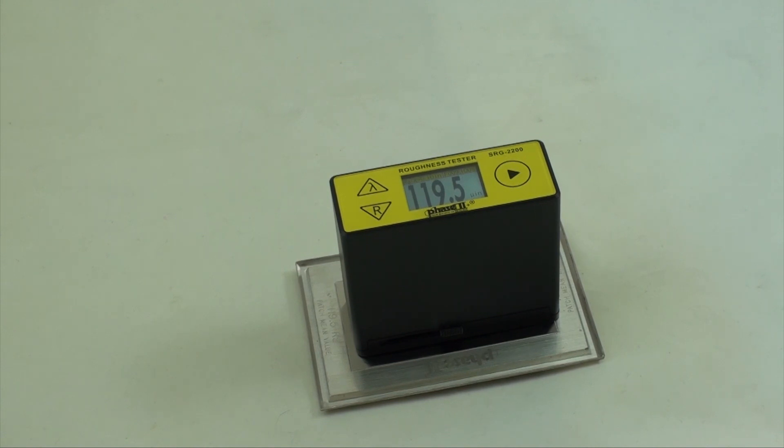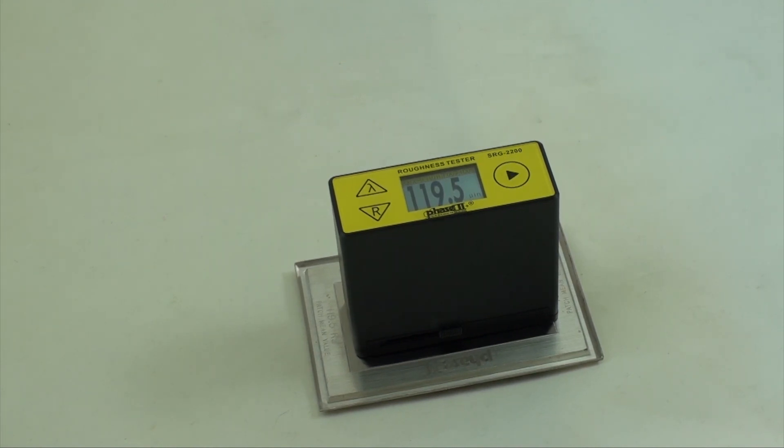When abnormal errors are found, the supplied reference standard should be used for calibration. The RA value of the supplied standard is 119.5 micro inches or 3.03 microns.